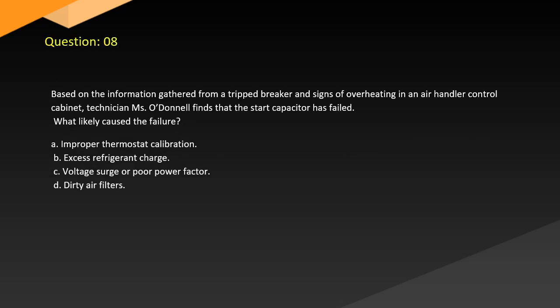Question 8. Based on the information gathered from a tripped breaker and signs of overheating in an air handler control cabinet, technician O'Donnell finds that the start capacitor has failed. What likely caused the failure? A. Improper thermostat calibration. B. Excess refrigerant charge. C. Voltage surge or poor power factor. D. Dirty air filters.